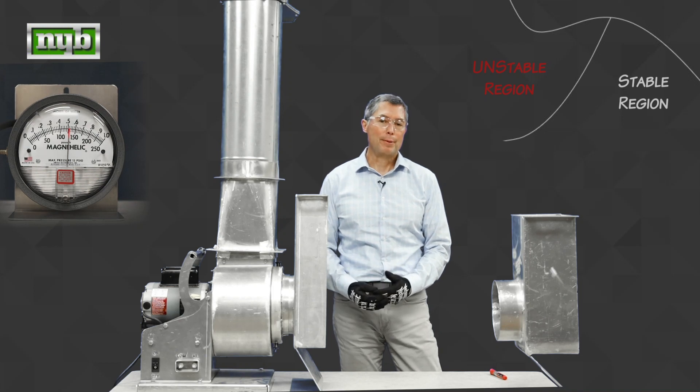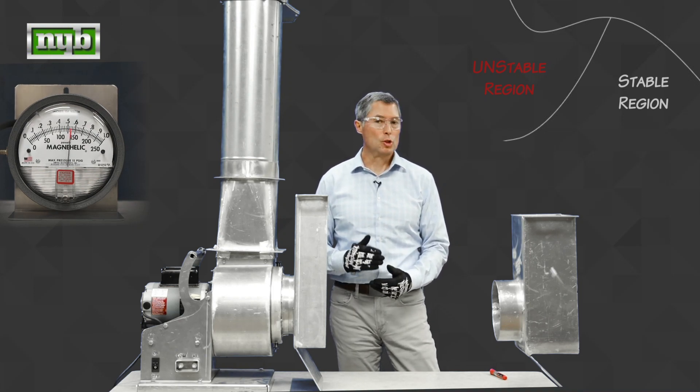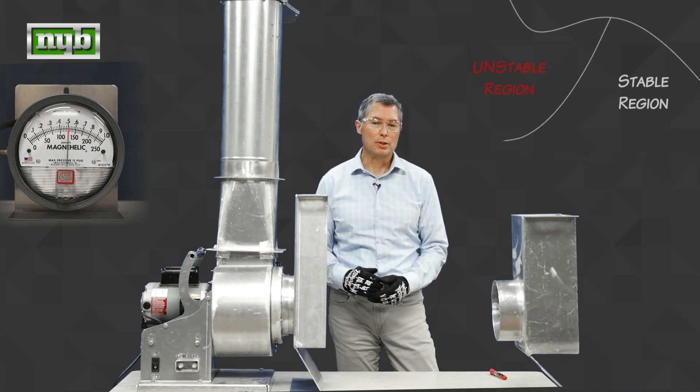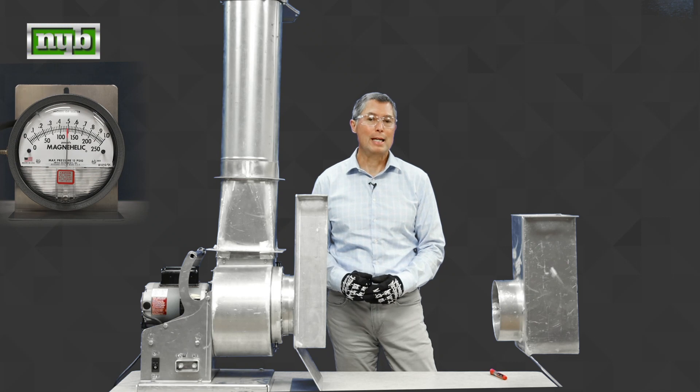That's going to be a problem if you have an application that requires very steady flow. So, for example, if you have a combustion air system, that can cause some pretty big issues with the flame that's being used to keep the process.